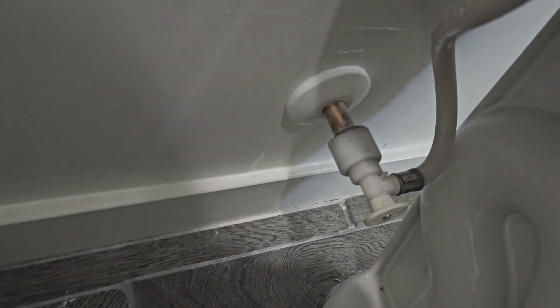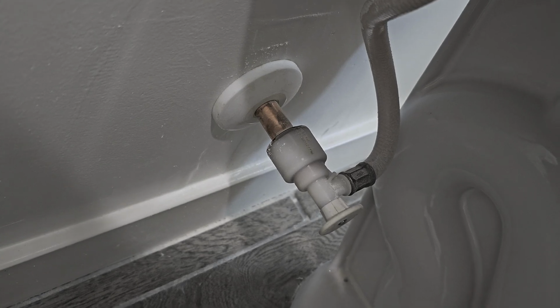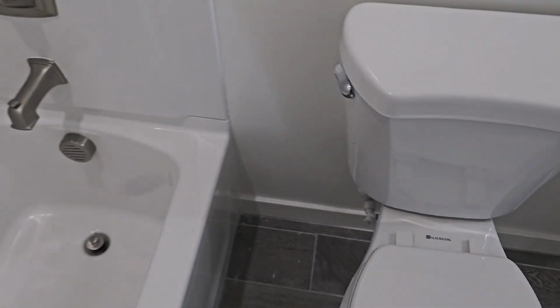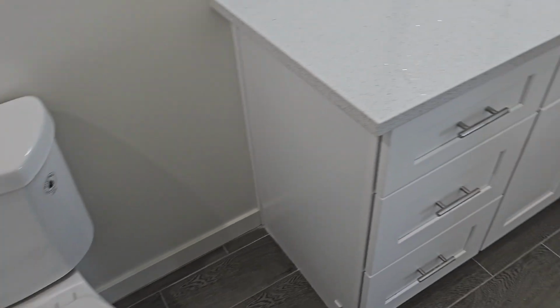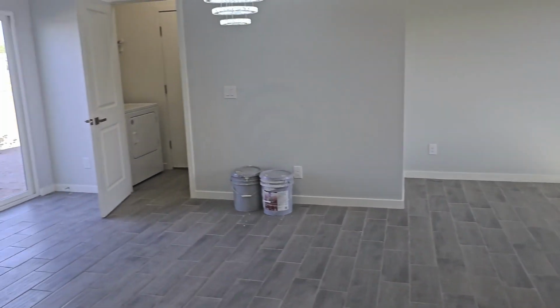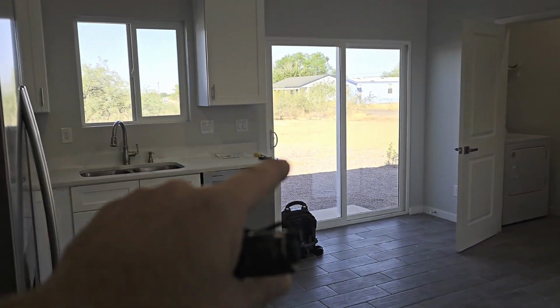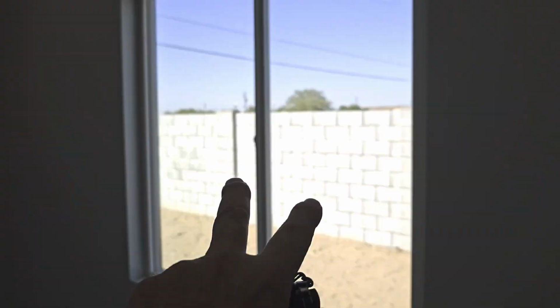You'd think it's all PEX, but behind the toilets it's copper. Yeah, you'll see a combination of that. It says non-metallic plumbing because they don't want you to rely on the plumbing to be a good bond. They want you to know it's partially non-metallic, and once you put some plastic plumbing in your house, it's considered non-metallic plumbing. Just because you can't bond those pipes - you can't bond copper through PEX into another copper. It has to be consistent copper, otherwise the bonding is worthless.